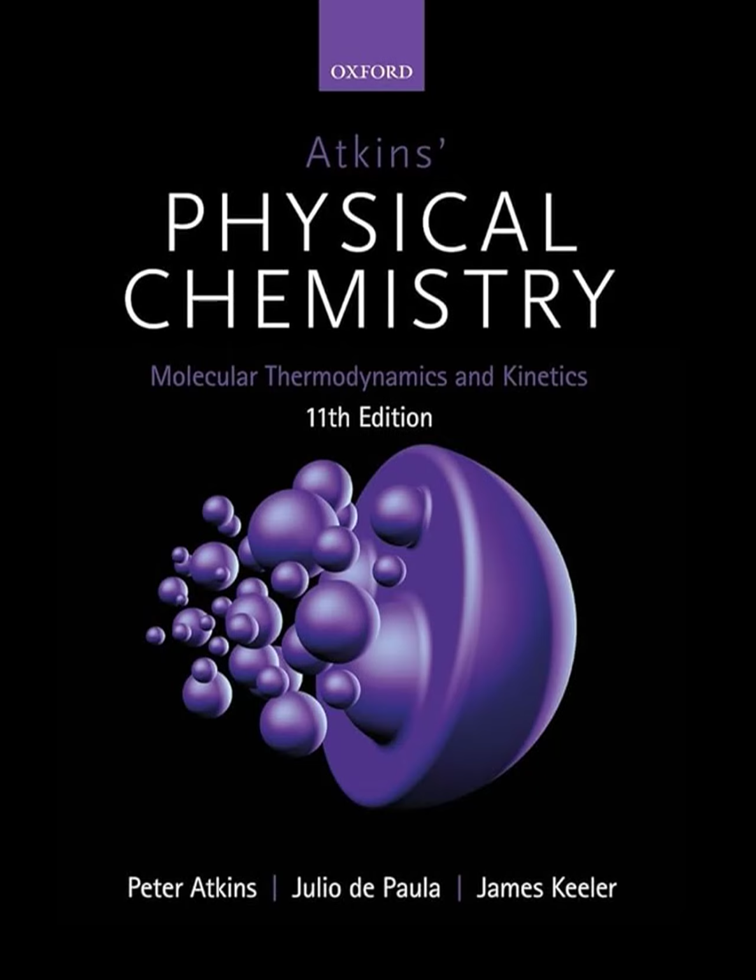But the FID is messy, right? It contains all the frequencies mixed together. It's in the time domain. Correct. It's a complex interference pattern over time. To get our familiar spectrum, intensity versus frequency, we need to mathematically disentangle those frequencies. And that's where the Fourier transform comes in. Precisely. It's a mathematical algorithm that converts the time domain signal, the FID, into the frequency domain signal, the spectrum. It's incredibly efficient and allows us to get spectra much, much faster than the old scanning methods.